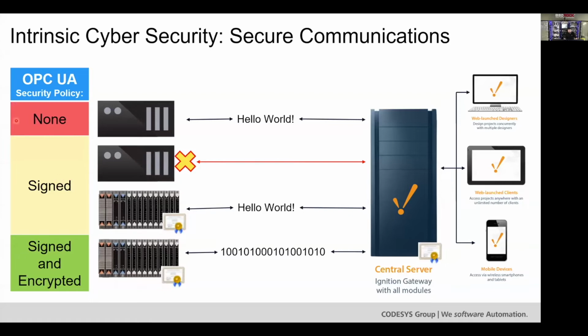As you move down the line with security policies, you can have signed data. This means you'll require a certificate on both sides of the controller to authenticate it to the server. If you have a server certificate on the server side but not on the client side, that connection will be rejected—you won't be able to connect in that configuration.